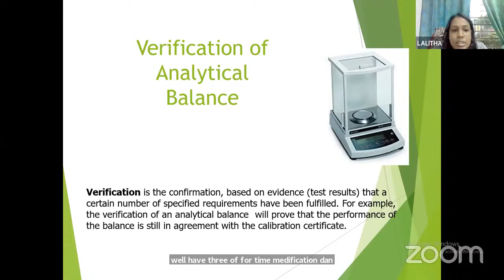Select the standard calibrated weights for various balances based on the capacity and operating range of the balance, as mentioned in the worksheet, and check the calibration status. Before verifying the balance, clean the weighing platform and pans with dry tissue or dry cloth. Adjust the balance to 0.